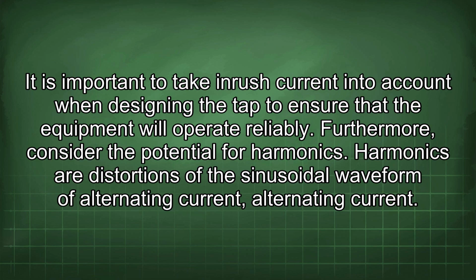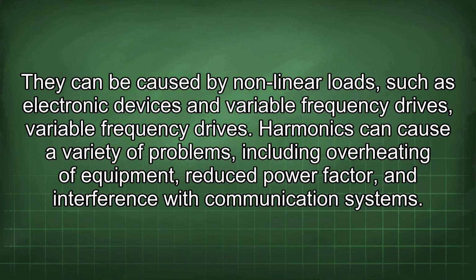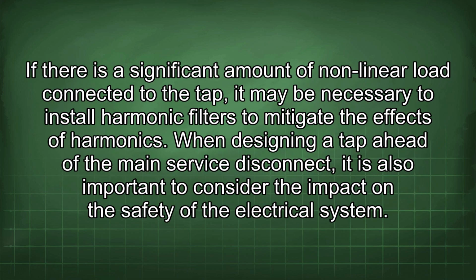Furthermore, consider the potential for harmonics. Harmonics are distortions of the sinusoidal waveform of alternating current. They can be caused by nonlinear loads, such as electronic devices and variable frequency drives. Harmonics can cause a variety of problems, including overheating of equipment, reduced power factor, and interference with communication systems. If there is a significant amount of nonlinear load connected to the tap, it may be necessary to install harmonic filters to mitigate the effects of harmonics.